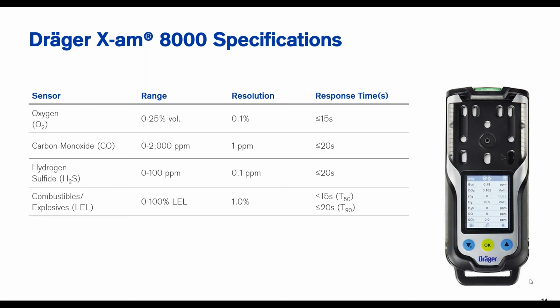And so it may be done in 2 or 3 seconds, but that just gives you a heads up, a general idea. And again, refer to your user manual, operator manual, to see what the specifics are for your individual meter. It will tell you, whether it's a catalytic bead Wheatstone bridge sensor or an infrared sensor, based on each individual sensor, what that T90 or T50 response time is. So it's important to make sure that you're looking at the appropriate time frame.